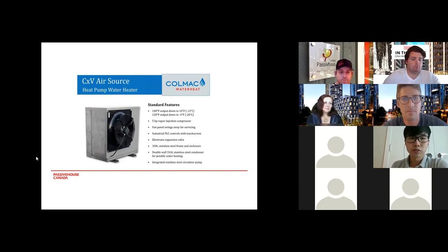The original domestic hot water system was just localized electric water heaters on each floor, located close to the terminal plumbing fixtures to minimize domestic hot water piping lengths. This solution allowed us to eliminate the domestic hot water riser, and also get rid of the domestic hot water recirc piping system and the recirc pump.